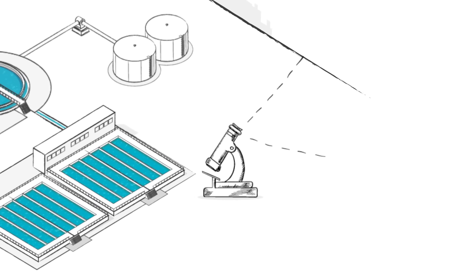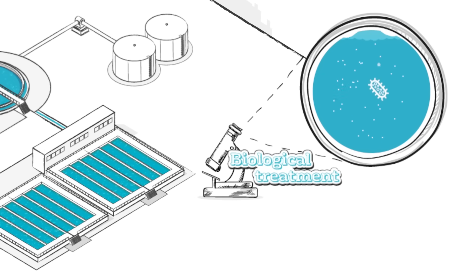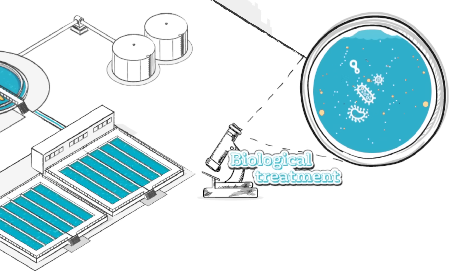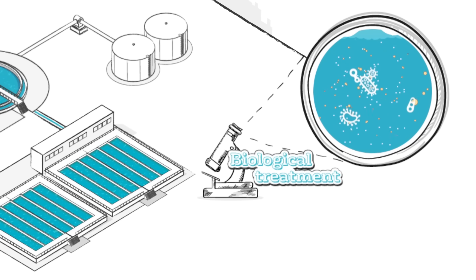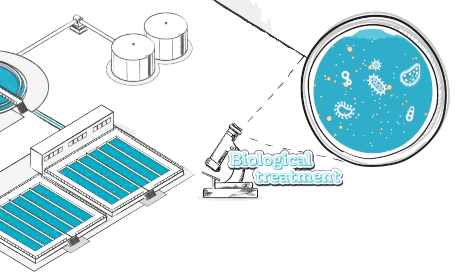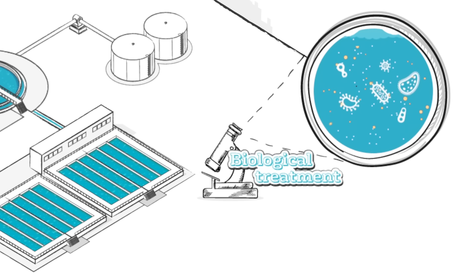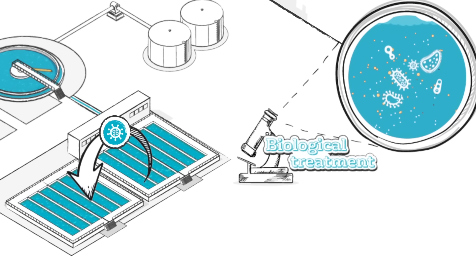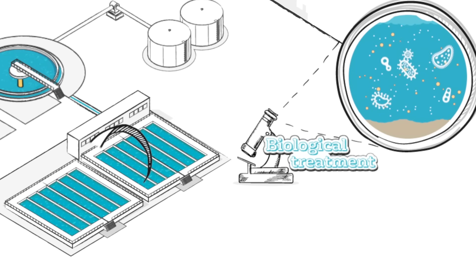Following this, the partially treated water begins biological treatment. Microscopic organisms that naturally occur in the wastewater break down the organic material. Air is pumped into the aeration tanks to encourage the bugs to reproduce and consume the organic material. The newer bugs go back to the aeration tank to live out the rest of their life cycle.